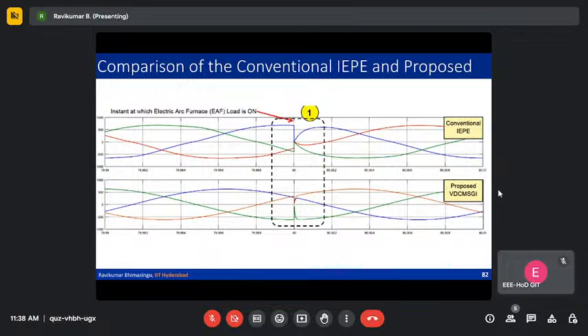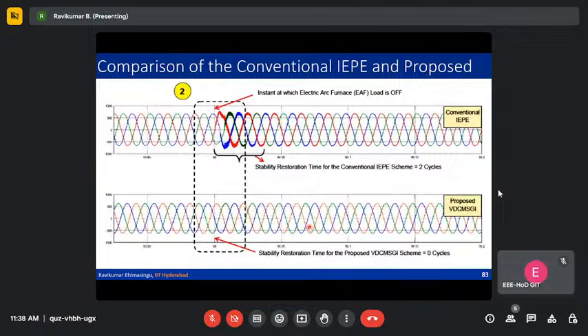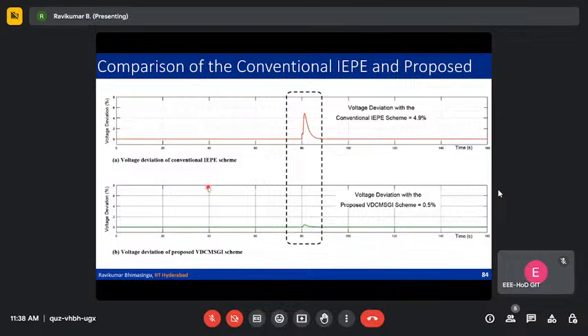You can clearly see the waveform shape of the conventional IEPE method and the proposed method. The waveform distortion is also limited in the case of the proposed method. And this is the instant at which the electrical arc furnace load is off. In the conventional method, immediately when the electrical arc furnace load is off at 90 seconds, the waveform got distorted, and to come back to normal operation it took almost 2 cycles, but it is very instantaneous in the case of the proposed method. For voltage deviation, the conventional IEPE has 4.9 percent, whereas the proposed method is limited to 0.5 percent.